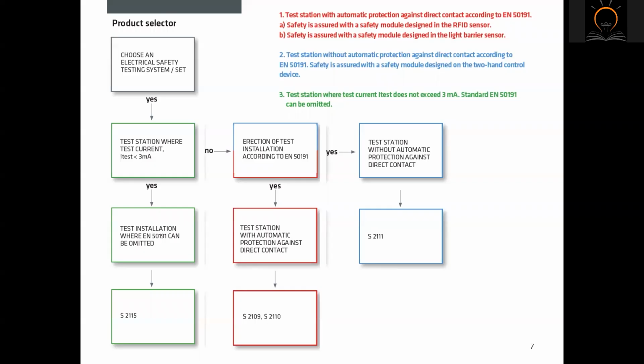Using the product selector table, we can decide which type of test station is most suitable for a particular area. If we are not forced to use test currents higher than 3 mA for the HV test, we can omit the requirements from EN 50191. Following the green code in the flowchart will lead us to the selection of S2115, a test station with current limitation.